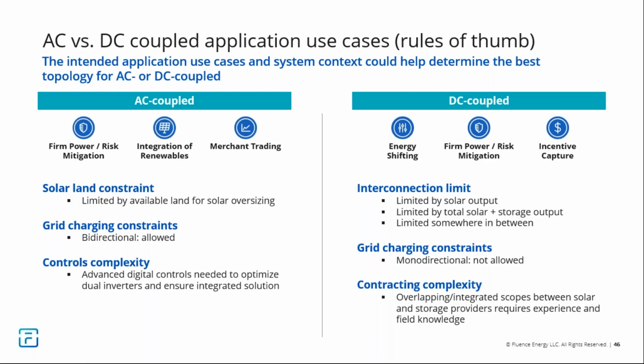On grid charging constraints, if it's a monodirectional asset not allowed to charge from the grid, that favors DC coupled, so you can capture that clipped energy - it won't be able to capture merchant trading or ancillary service revenues significantly. A bidirectional asset could favor either, but may open up more opportunities for AC coupled.